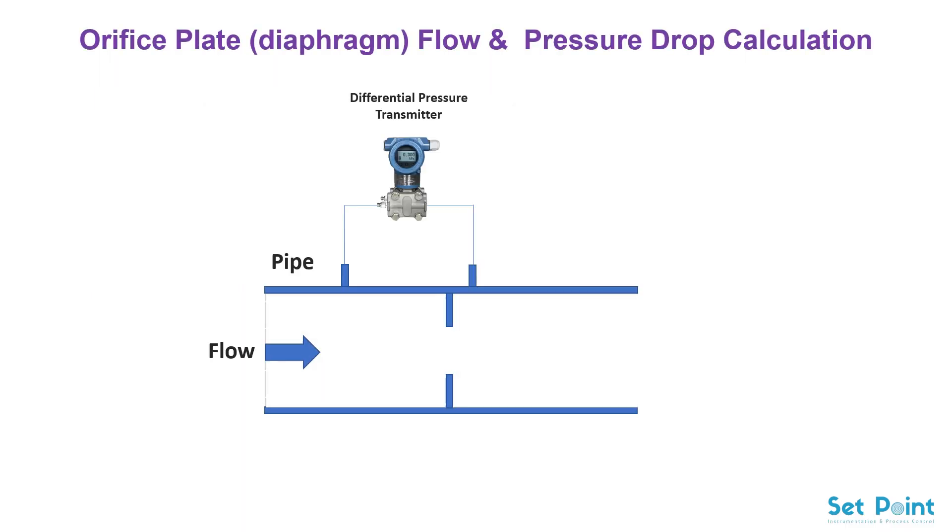The primary element, often called a square-edged orifice plate, consists of a flat piece of metal with sized hole bored in it, creating a dp across it. The square root of the dp is proportional to flow.